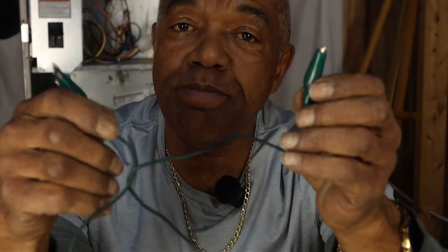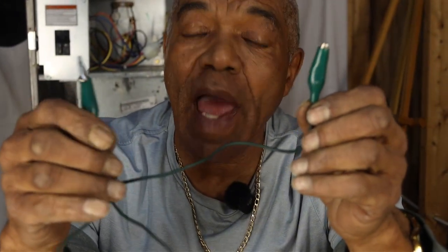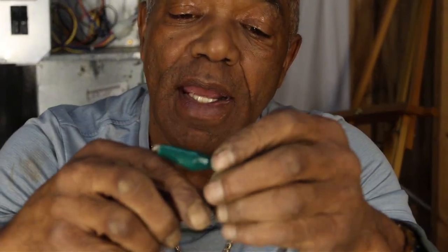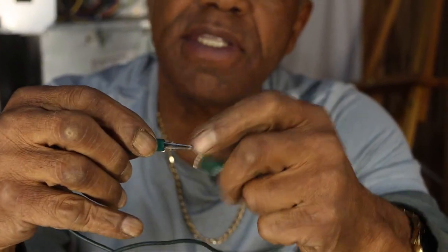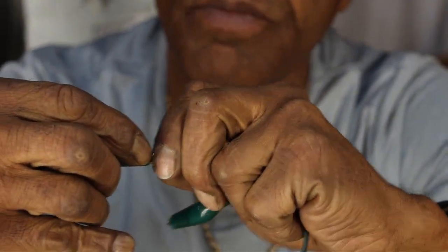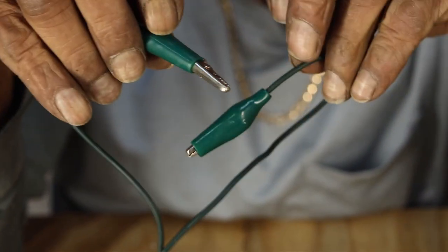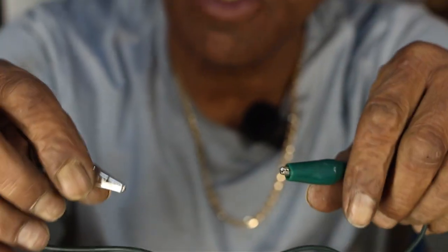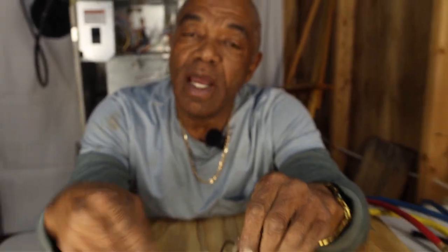Along with this, you often want to have alligator clamps, okay? These you can buy for about $6. You get about 8 of them in a pack, all different colors. You get red, you get blue, you get green and yellow and black, white. And what they do is they allow you to test things, bypass certain elements of the system. If I think I have a bad flame rollout switch, I can jump from one side to the other and verify was that the problem. I can jump out my pressure switch.